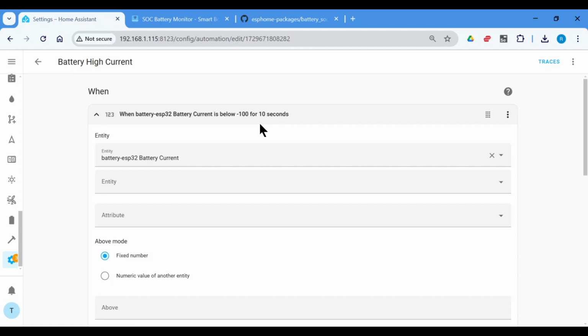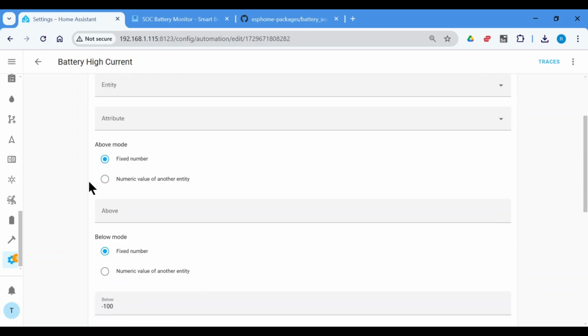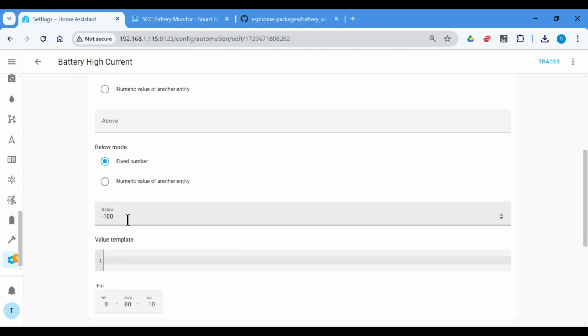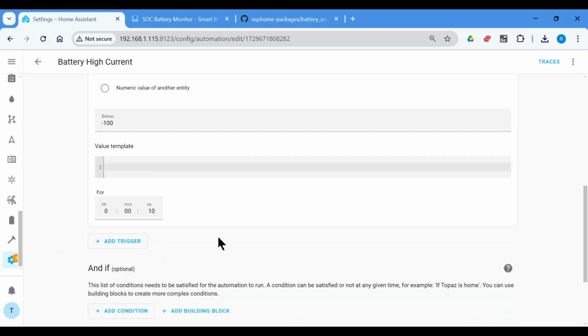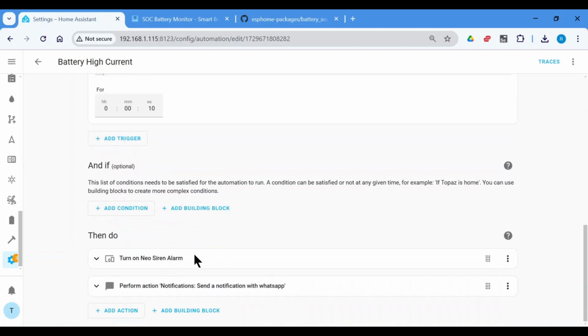You can change this 10 seconds, 5 seconds, depends on what your load is. I shouldn't have anything more than 100 amp discharge for more than a few seconds on my boat. So it's less than minus 100, and I have 10 seconds, and then I just have the action to turn on the alarm and send a WhatsApp.